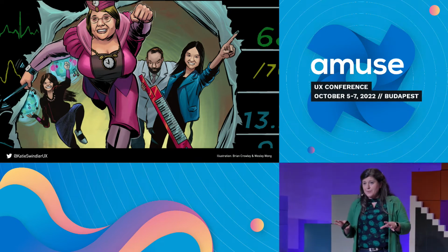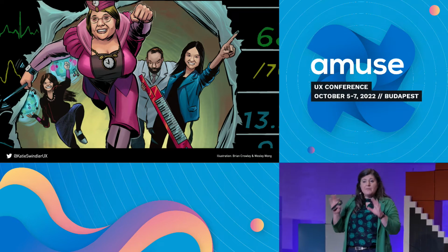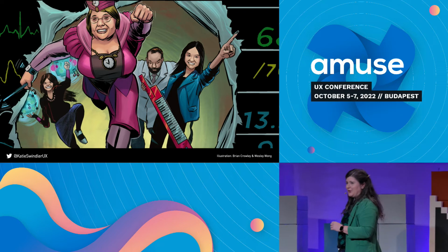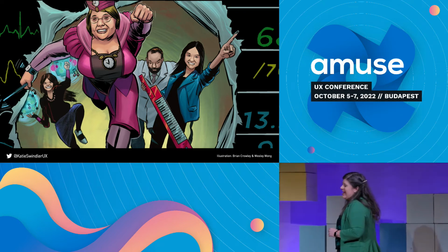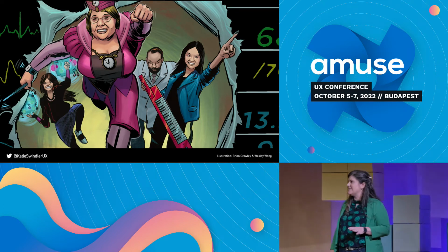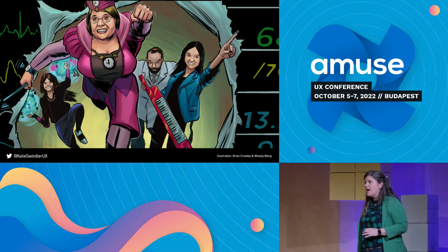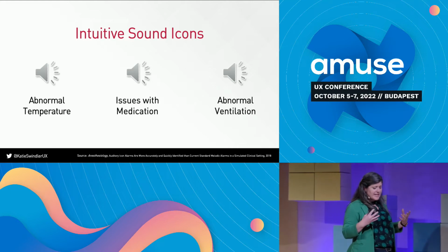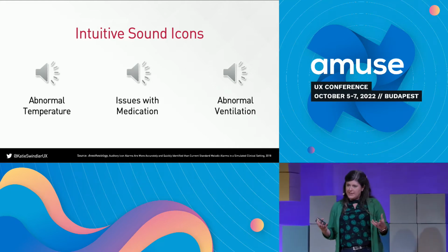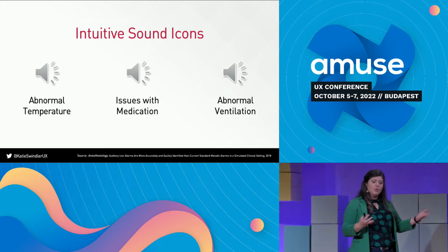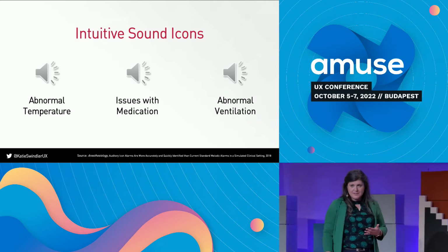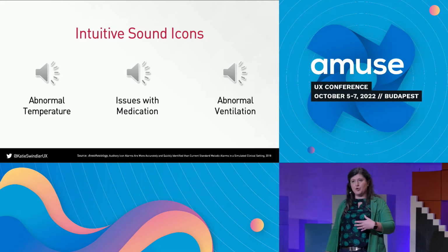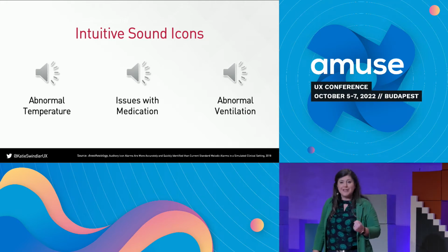But some of my favorite work was done by a woman named Dr. Judy Edworthy. She was called the godmother of alarm design by the New York Times. And she and her colleagues did some really interesting work creating what they called sound icons. What they did is they took sounds from everyday life and paired them with associated alert concepts. For instance, the sound of a rising tea kettle might tell you that your patient's temperature is getting too high.